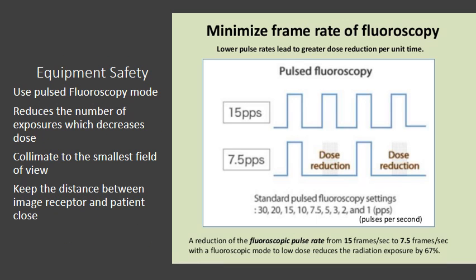So pulsed fluoroscopy exposure means that short bursts of exposure, 3 to 10 milliseconds, are used for visual checks rather than keeping the exposure on mode. This is sometimes referred to as intermittent fluoroscopy. And so this chart shows the different pulses at 15 or 7.5 pulses per second. And you can visually see these dose reductions. The exposure is about 1/2 the original pulse.